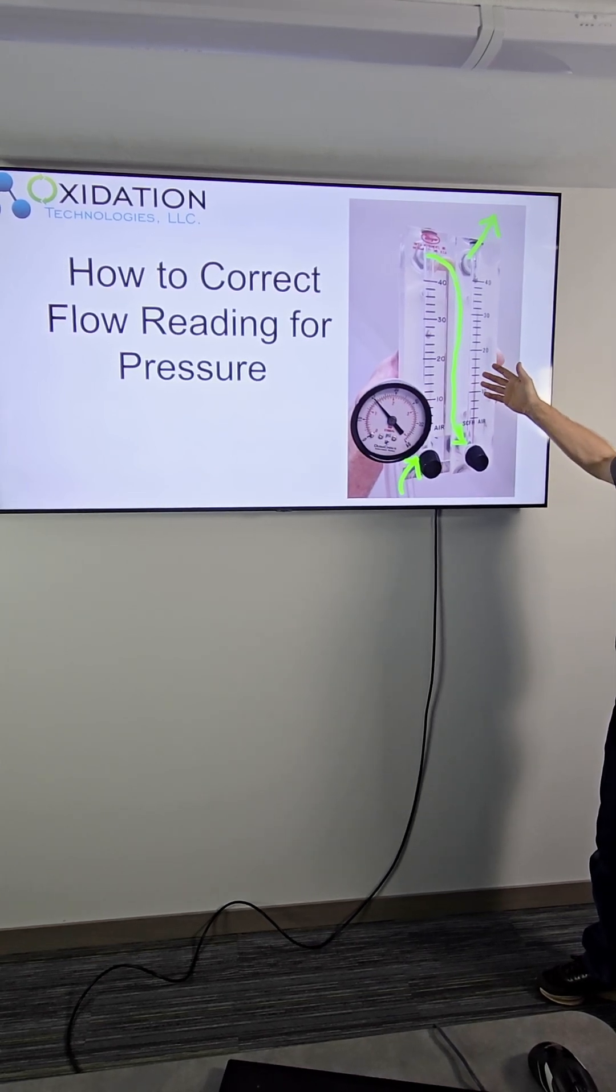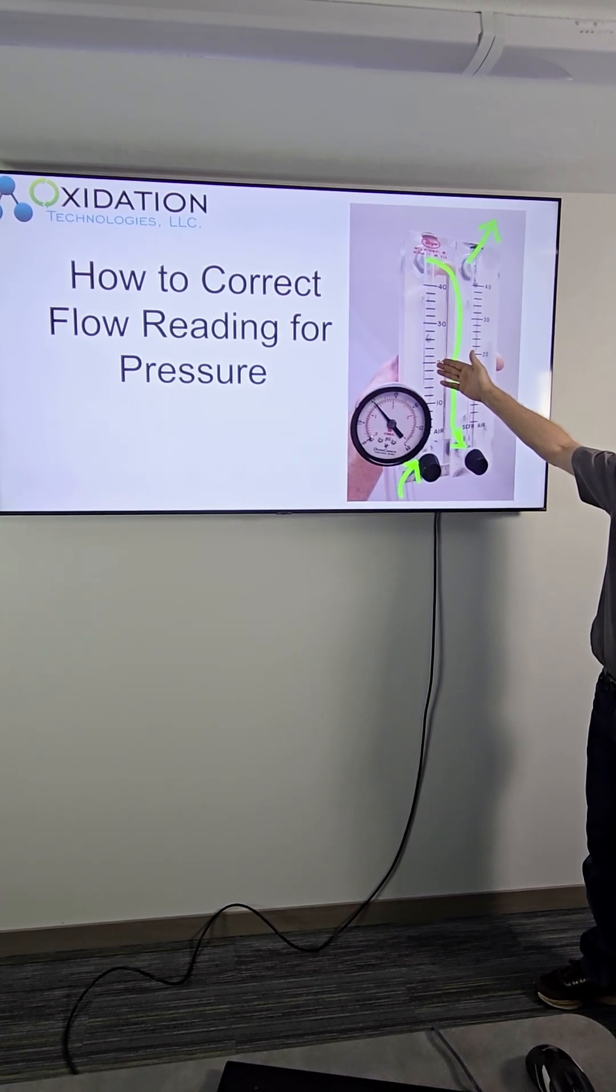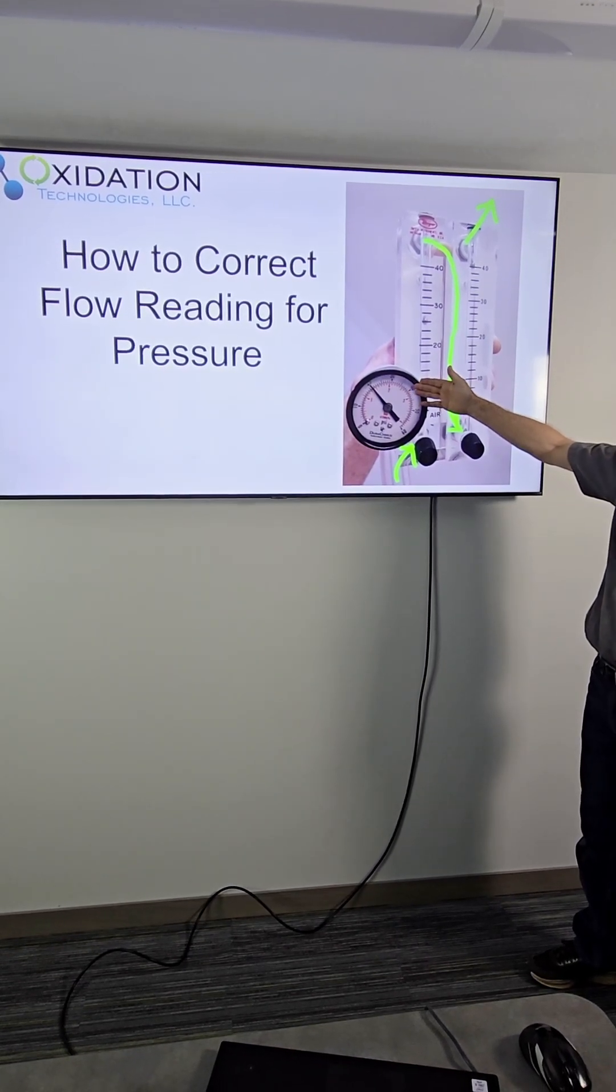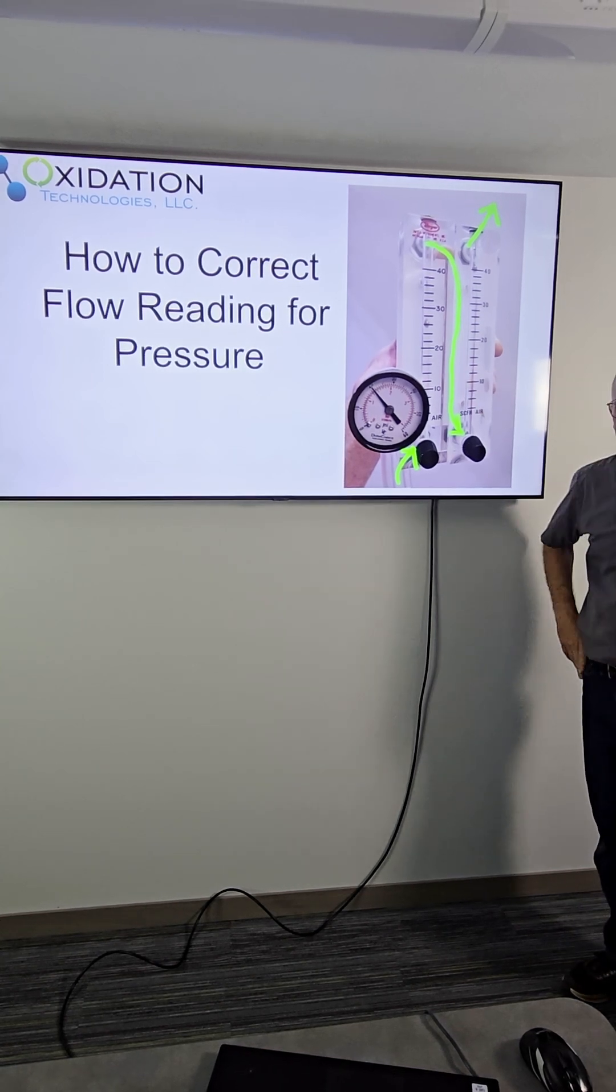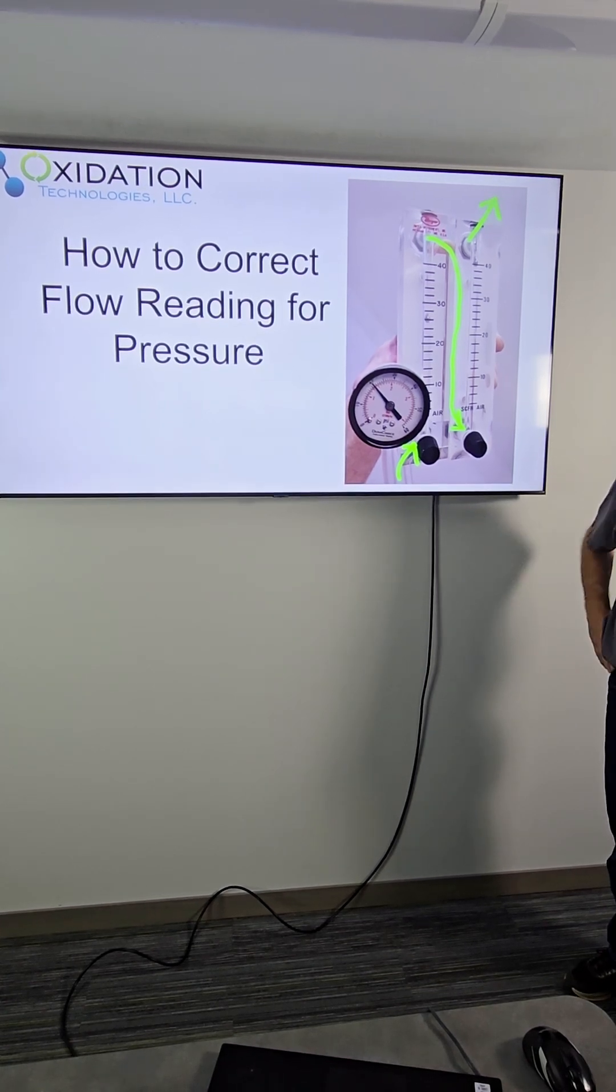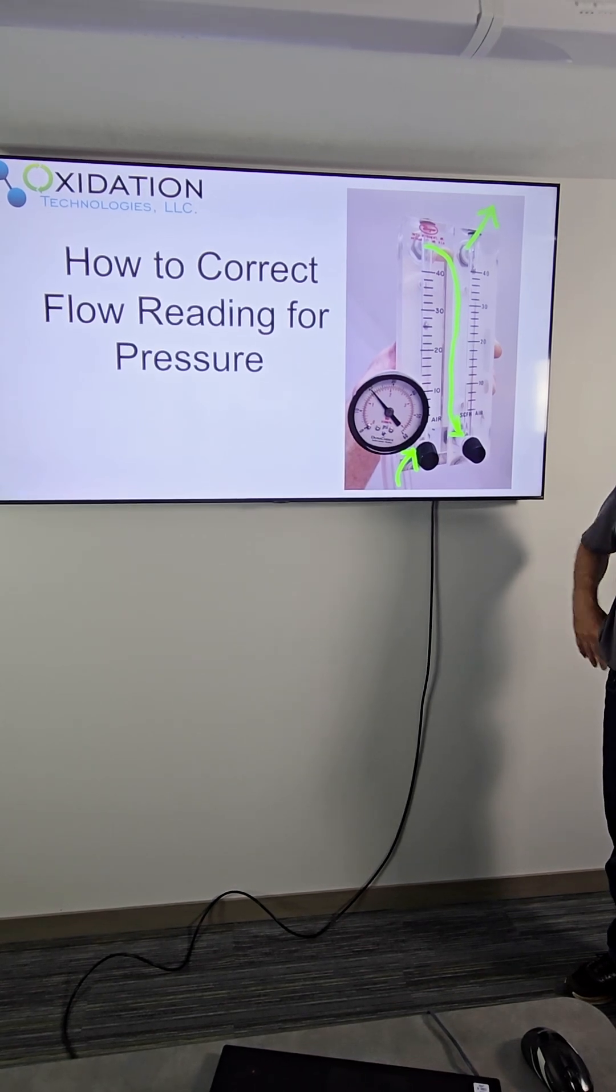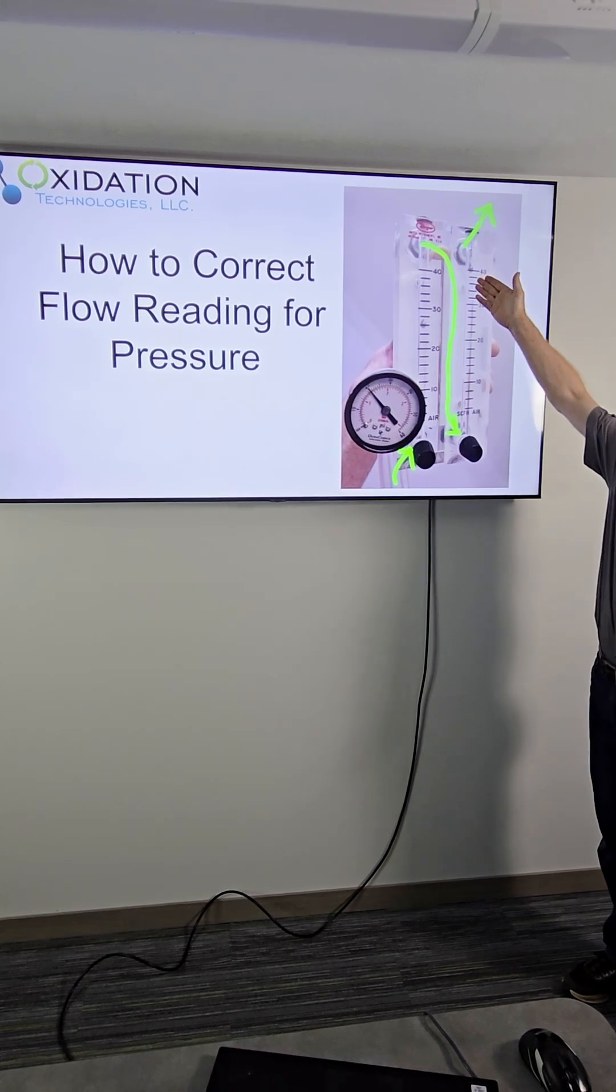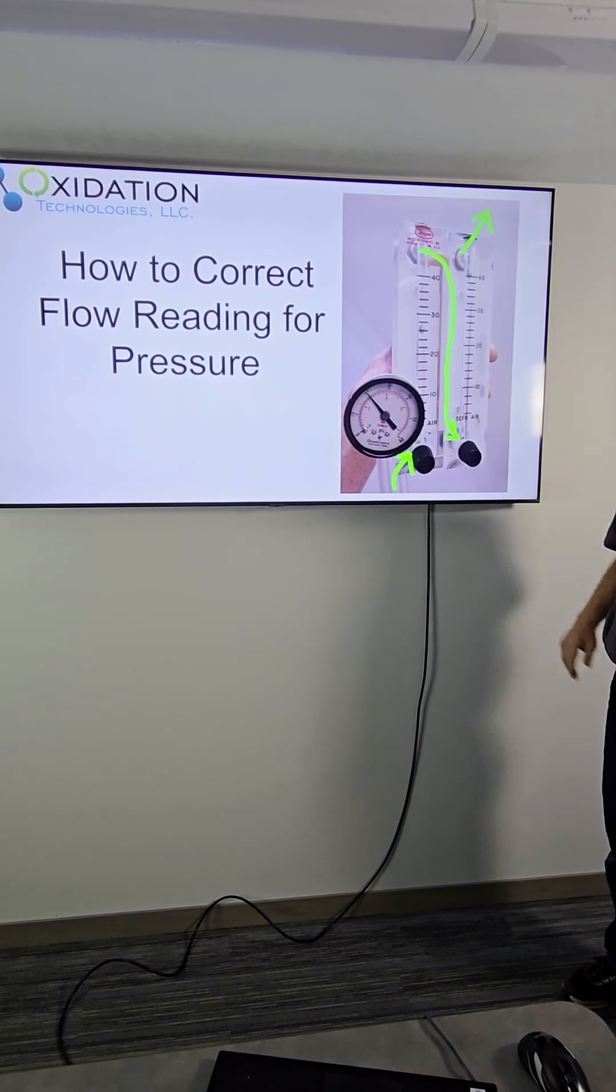They're both correct but when you're measuring gas under pressure you need to compensate, there's a calculation to correct for pressure. You can get flow meters that are already calibrated for a specific pressure. The flow meters that we use here at Oxidation Technologies, it's a range of pressures. They're all calibrated for atmospheric. So this one is giving you a correct reading. This one can be used just fine as long as we correct for pressure.